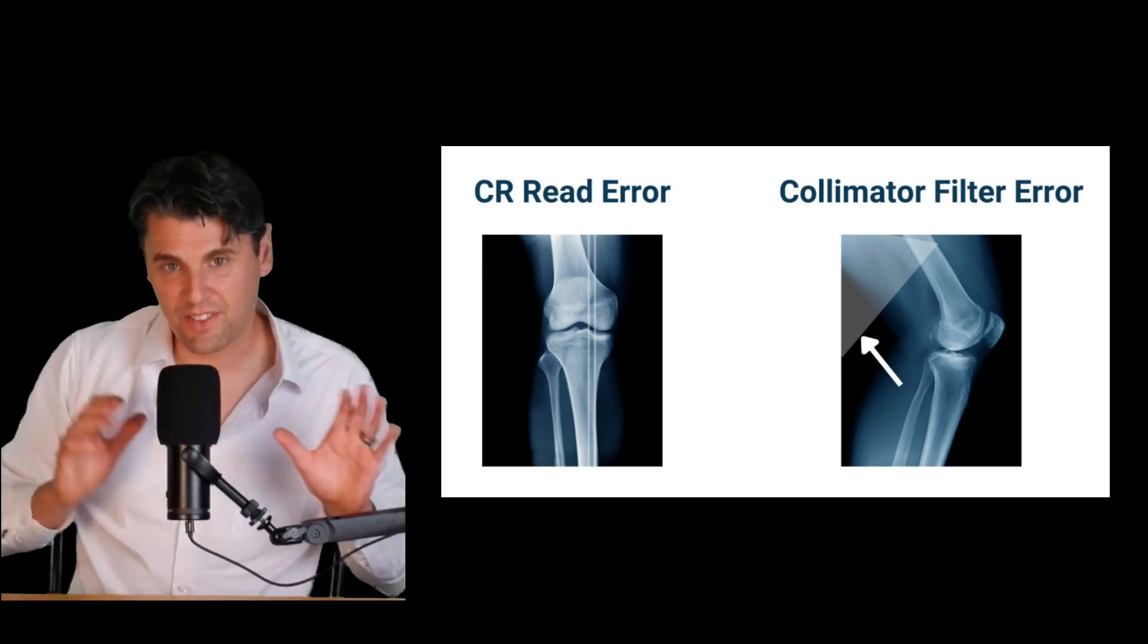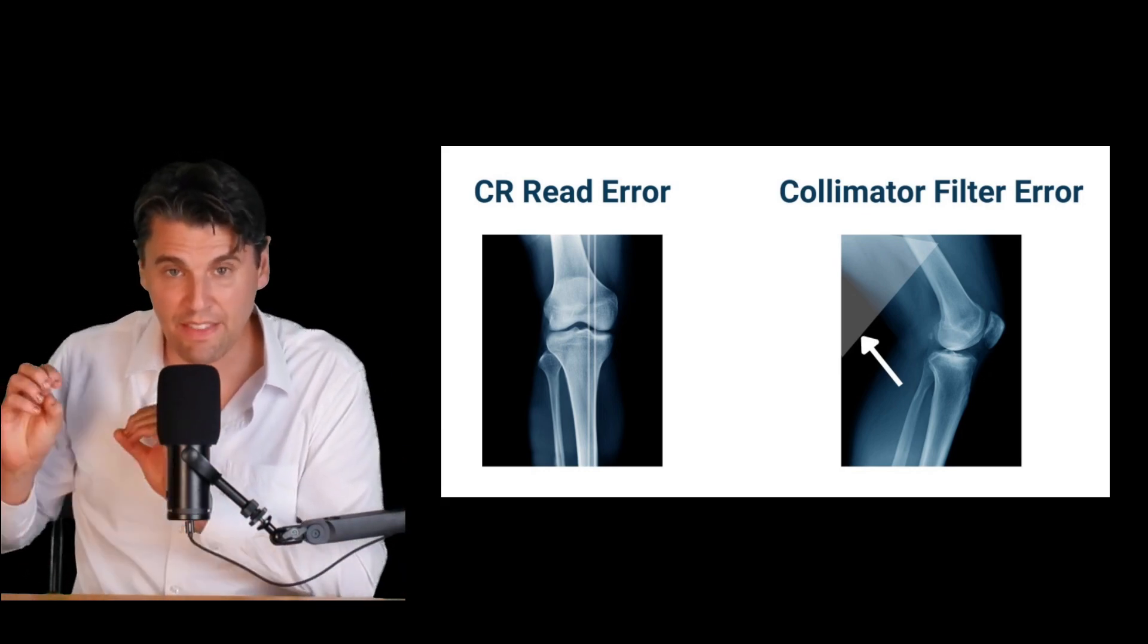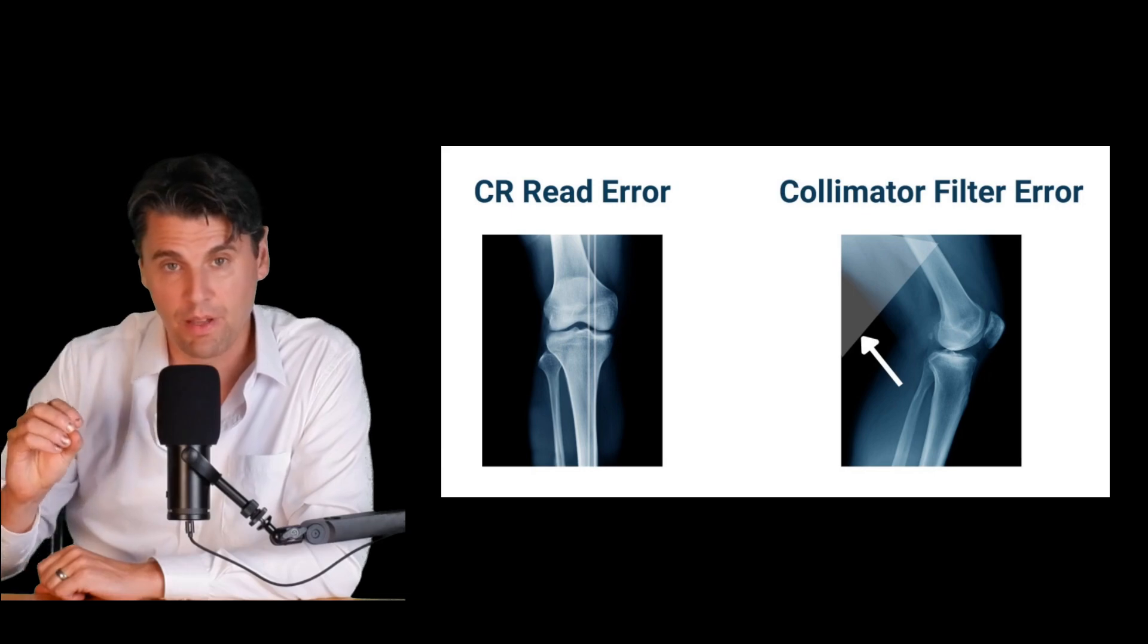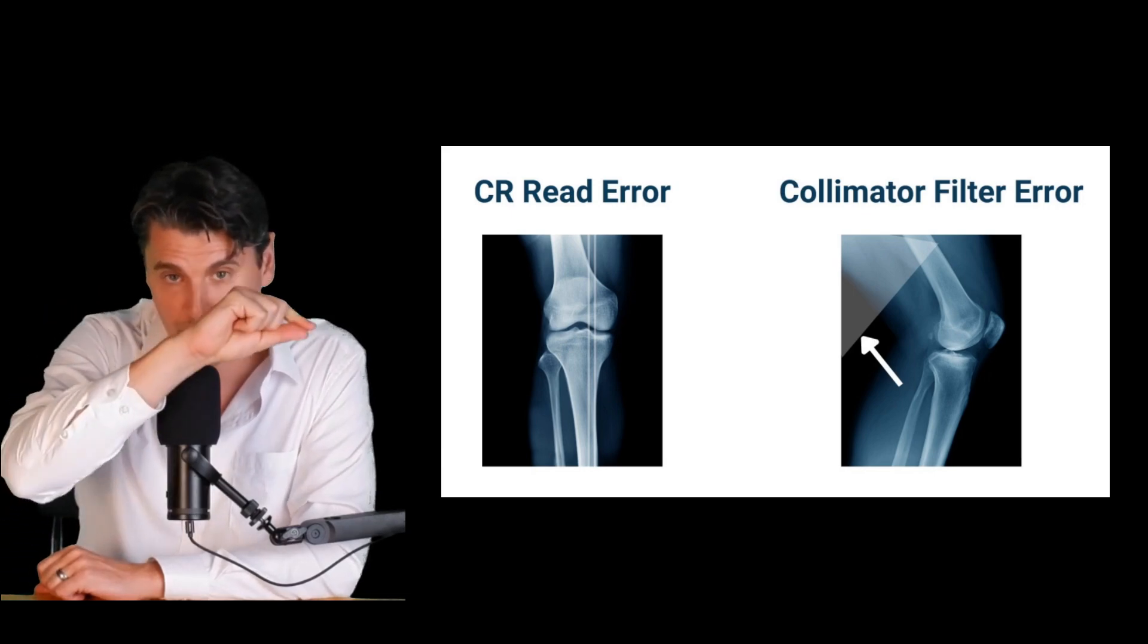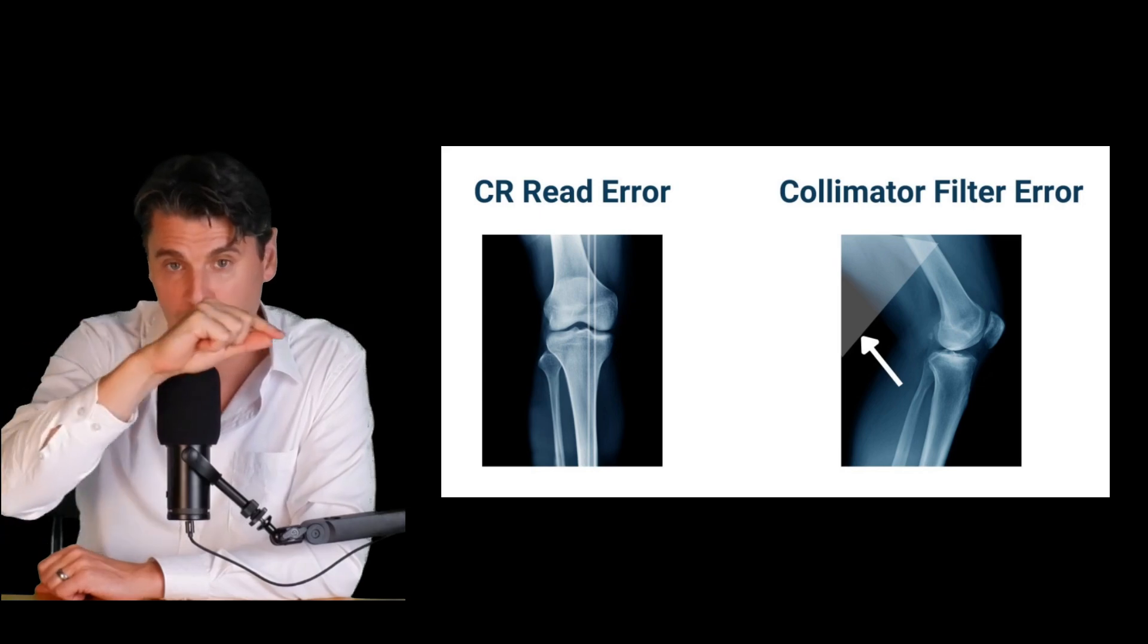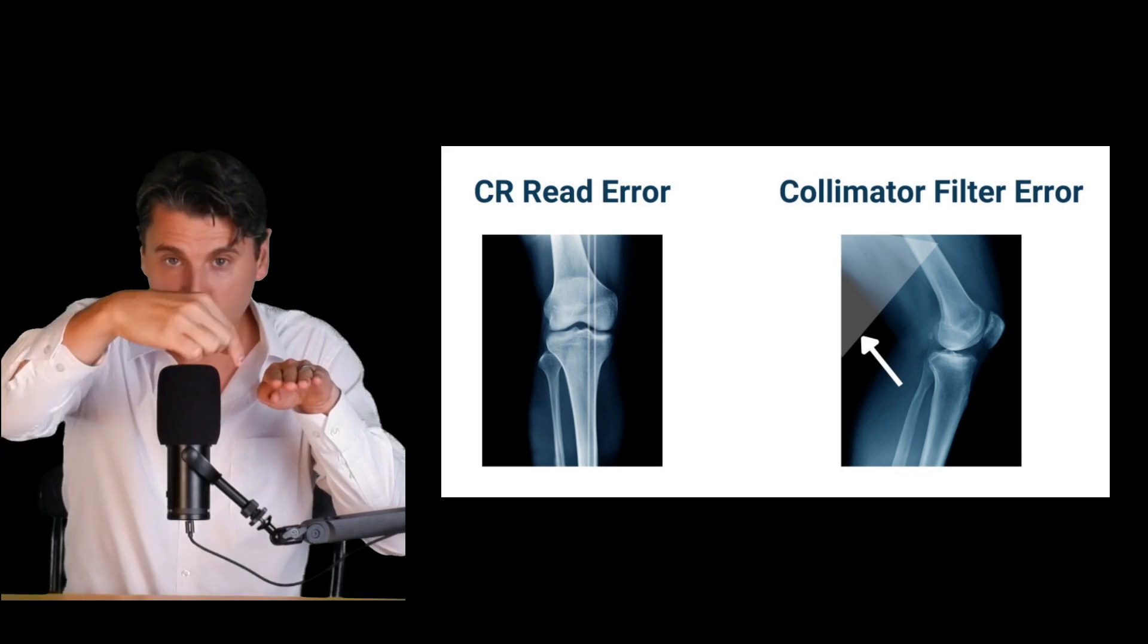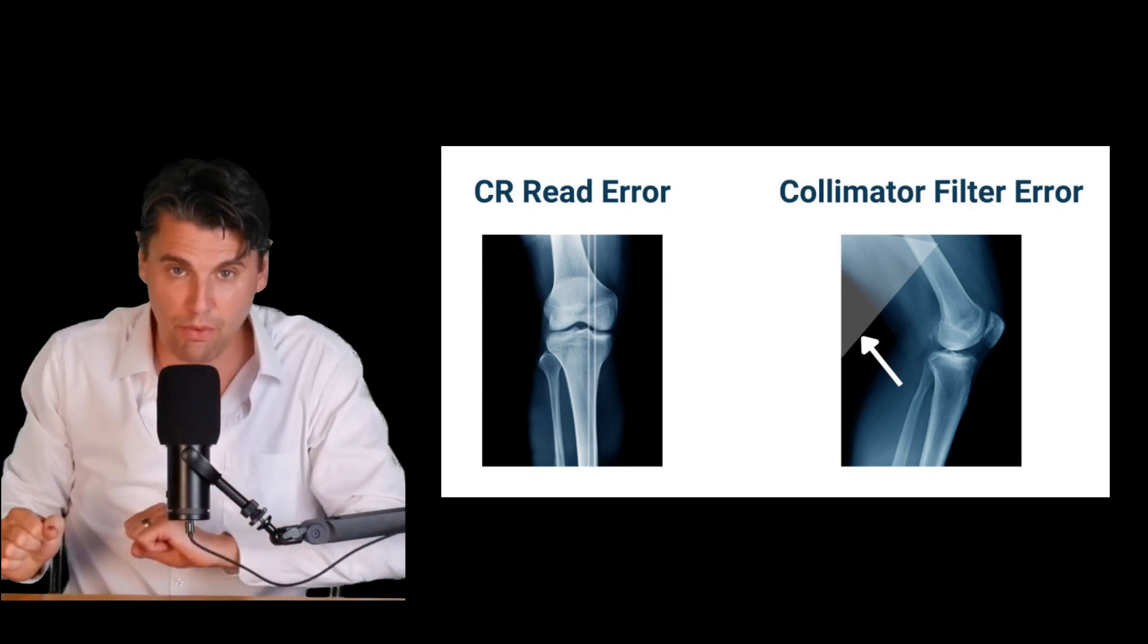Again on the CR side if you had an issue in the readout where for instance there was a problem reading out one of the rows, remember on a CR system you go across and you'll read out the panel then the whole panel will translate you'll read out another row the whole panel will translate you'll need to read out another row.